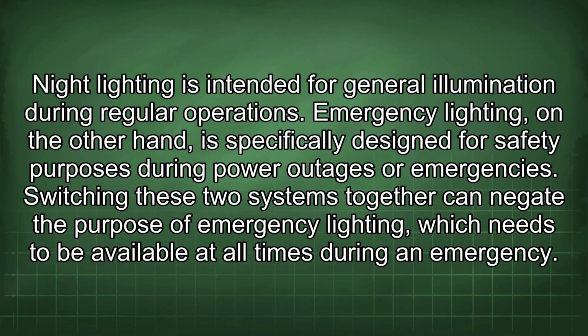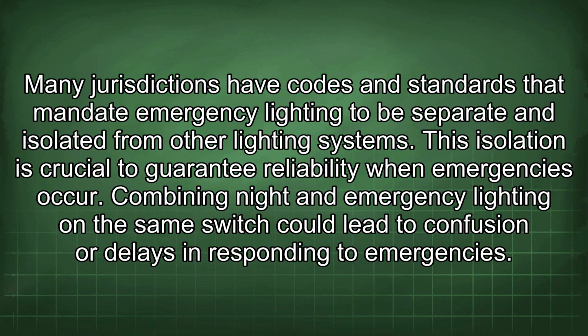Night lighting is intended for general illumination during regular operations. Emergency lighting, on the other hand, is specifically designed for safety purposes during power outages or emergencies. Switching these two systems together can negate the purpose of emergency lighting, which needs to be available at all times during an emergency. Many jurisdictions have codes and standards that mandate emergency lighting to be separate and isolated from other lighting systems. This isolation is crucial to guarantee reliability when emergencies occur.